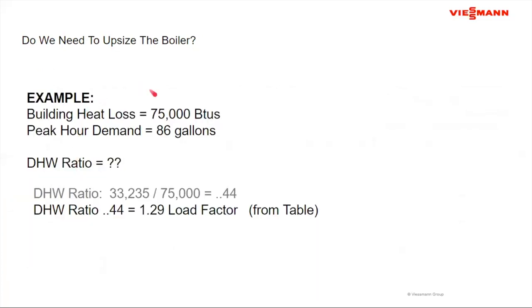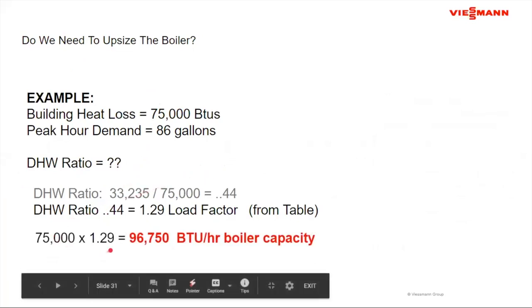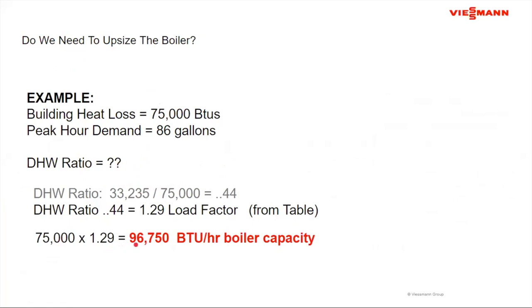So for instance, if I have 75,000 as my space heating load, my domestic hot water load is 33,000. That gives me a ratio of about 0.44. That 0.44, let's call it the load factor 1.29. I take my 75,000, I multiply it by 1.29. That's telling me that I need a 97,000 BTU per hour boiler to cover the load, again, if it's going non-priority. So now I've sized my boiler for the application.